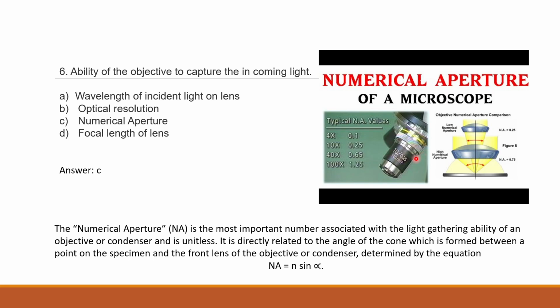So you can know for what objective lens what thickness you can use, because they have given it already. And then few will have some other marking like WD, that is working distance, like how far the length should be. Usually the recent ones do not have this. This is one of the limitations of a few lenses. And then some other properties, it will tell you whether you have to use oil immersion or air itself is enough.